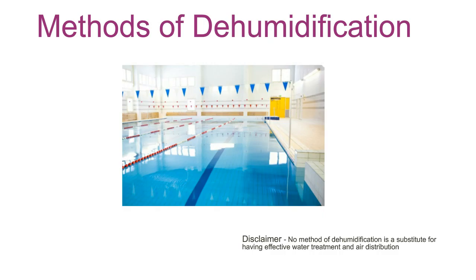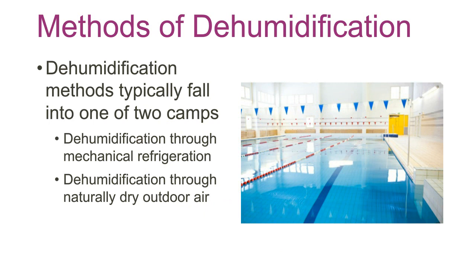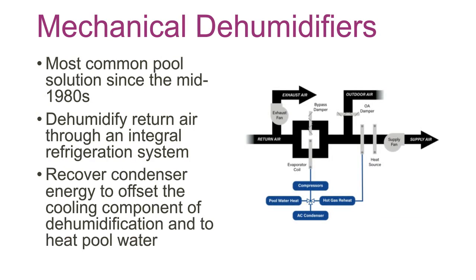I'd like to talk about some methods of dehumidification, and I did put a little note on the bottom that's important. It doesn't matter what dehumidification method you use, it's not a substitute for having effective water treatment and having effective air distribution. Those are very important regardless of the method that you use. Typically, I've seen they fall into two camps. Either you're using mechanical refrigeration for your dehumidification, or you're doing dehumidification through the dry outside air. Mechanical dehumidifiers have been the most common solution, I would say, since the 80s. They dehumidify return air with a refrigeration system and then recover the energy to offset the cooling that they did, plus heat some pool water.